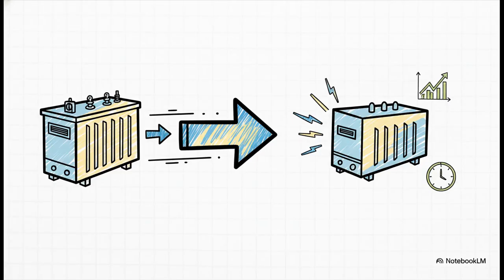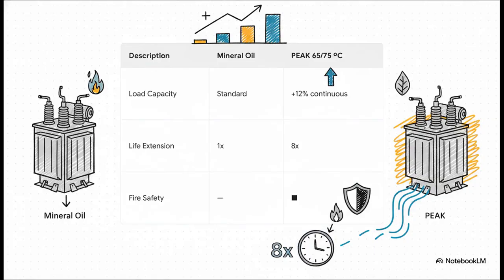What if you need even more performance, more muscle, and a much longer life out of that liquid-filled design? Well, that's where something called peak transformers come into the picture, and this is where things get really cool. By using a more advanced fluid and better insulation, these peak transformers can handle 12% more load continuously than a standard one.